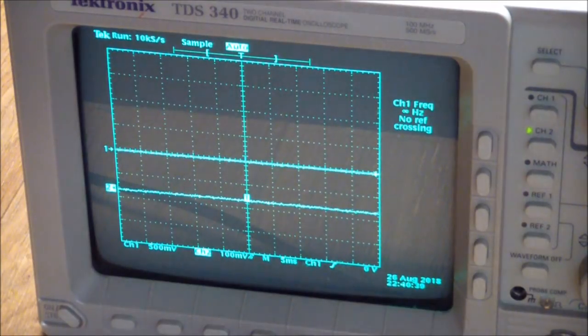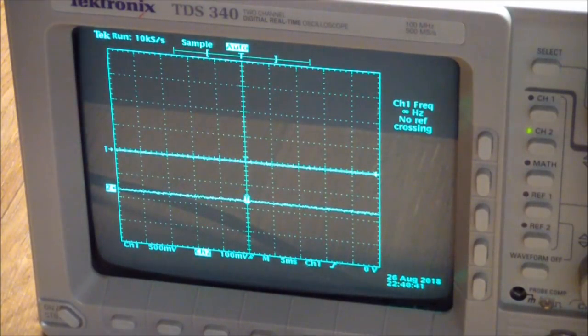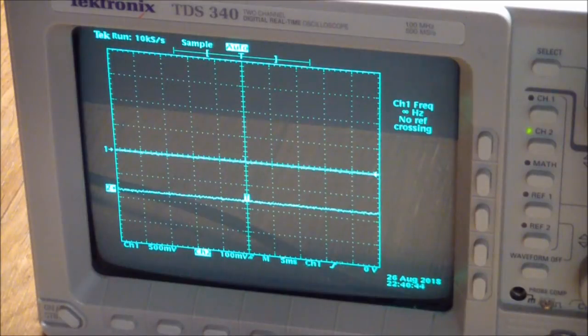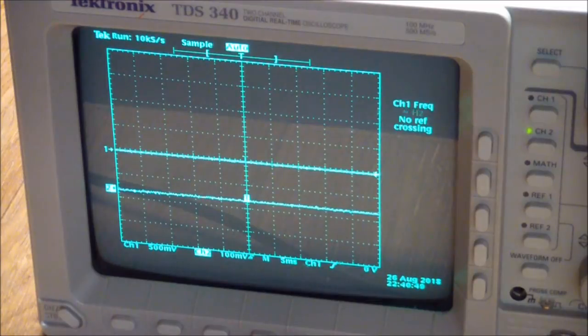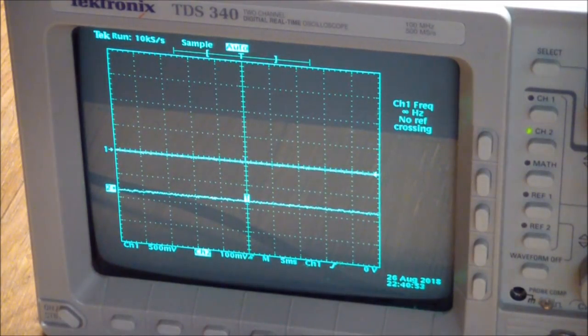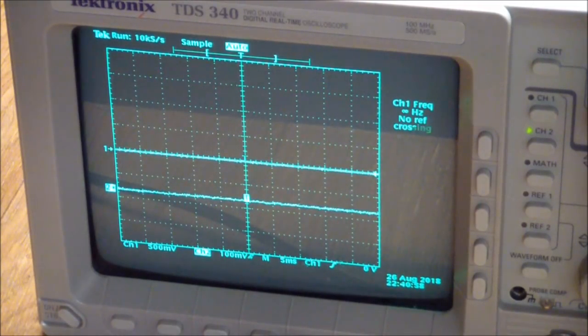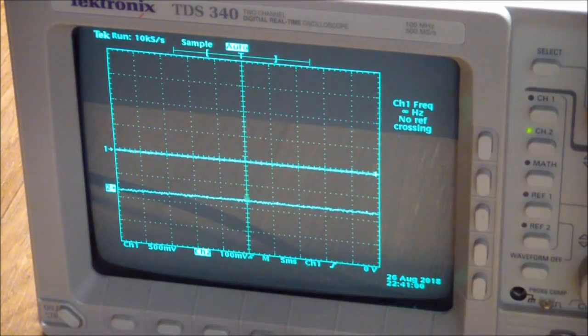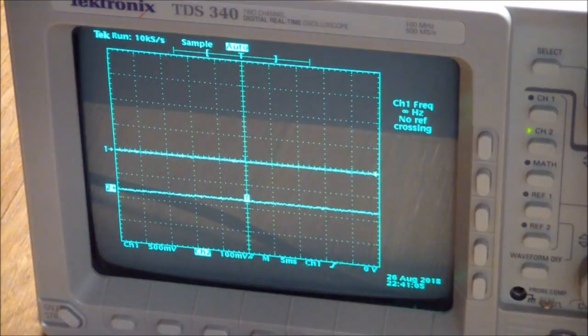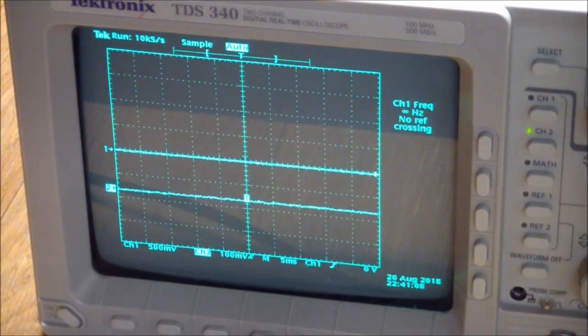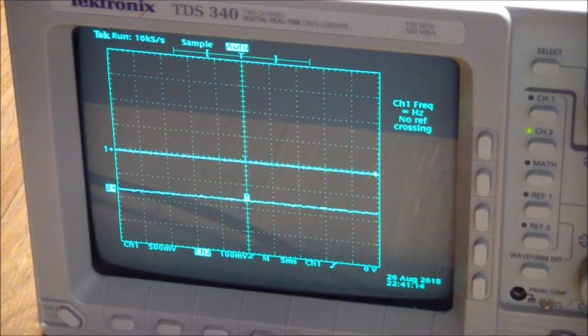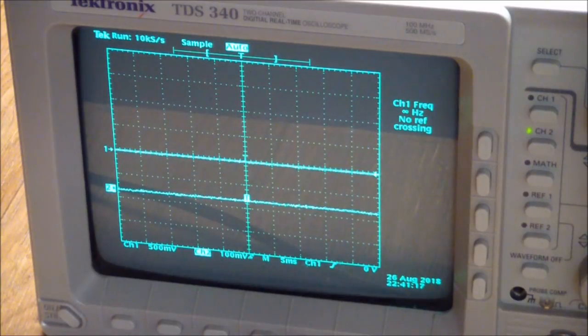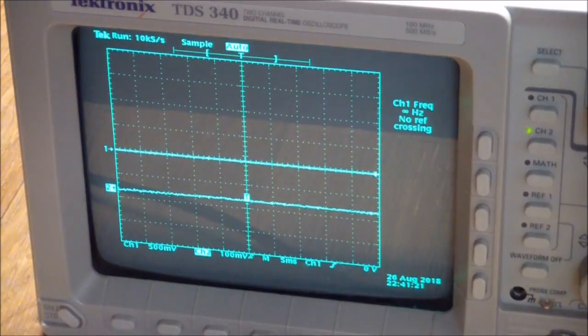Another thing I did while I was poking around the board before repairing it was just to make sure I took out the fan and plugged it directly into 12 volts to make sure it works. And it did work but it was pretty noisy, made a kind of a light grinding noise. But then I got distracted, did something else while the fan was still running and when I came back about 45 minutes later the fan was quiet. So it must have had dust in the hub and it just eventually blew it out because it's a normal sounding Tektronix fan now. Well let's check signals now.